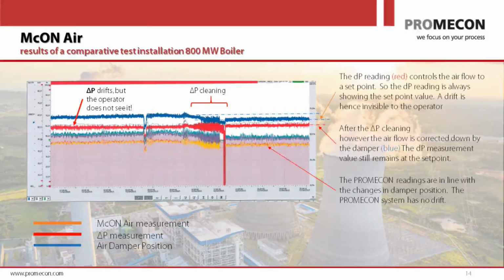However, before and after cleaning, same level. But not so the air damper. The air damper is the blue line. And on the blue line, you can clearly see before and after cleaning, 2 different levels, quite radically different levels. So this is a common problem that is very, very hard to detect. The yellow line below is our PROMECON measurement, which follows the damper pretty well because our measurement does not drift. It always follows the true airflow.